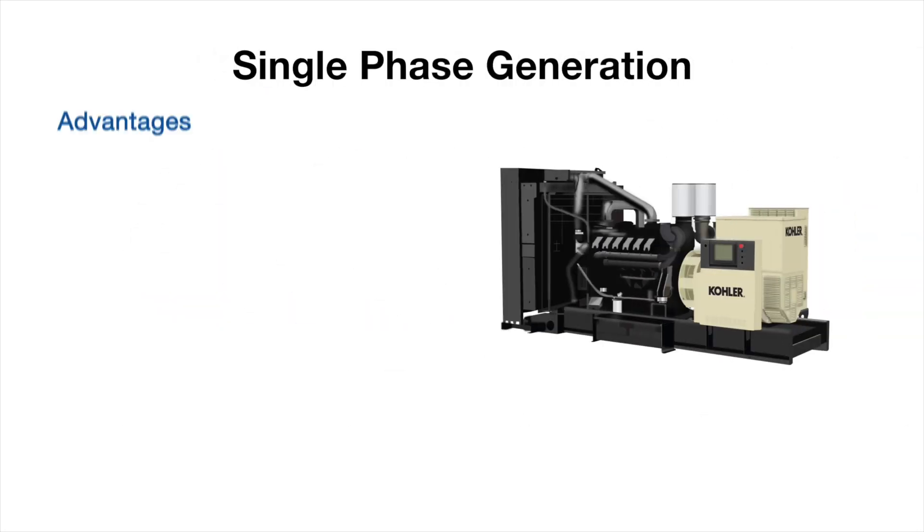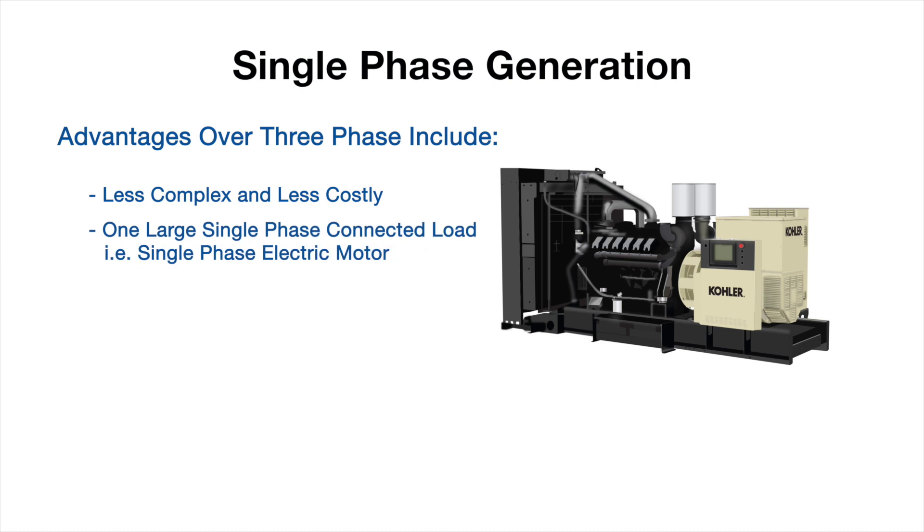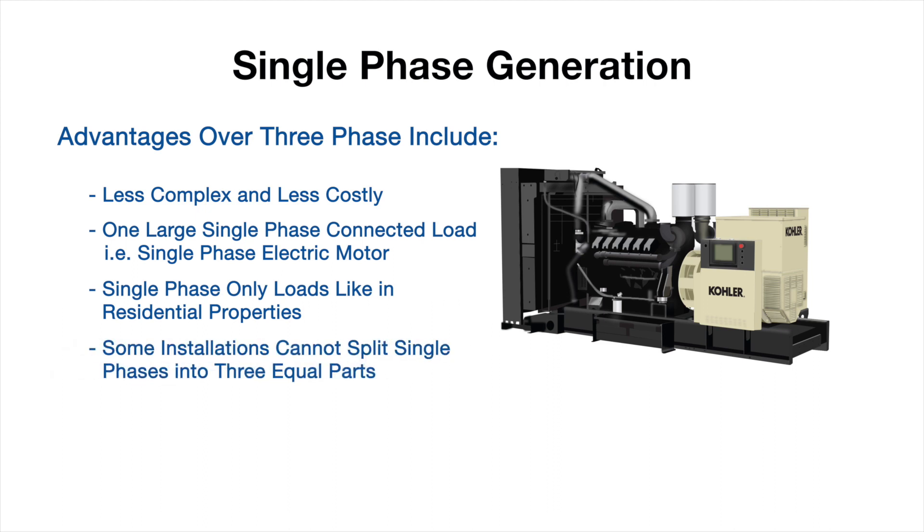There are some distinct advantages to using a single-phase system. Single-phase systems are less complex and less costly. A single-phase system should be used when you have a large single-phase connected load, such as a single-phase electric motor. Single-phase is better for small, single-phase-only loads like in residential properties. And some installations cannot split the single-phase loads into three equal parts for three-phase supply, so a single-phase generator must be selected.